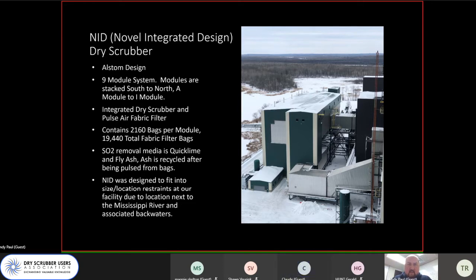It's a 9-module system with one redundant module, so we can maintain full load with 8 modules in service and take one out for maintenance. We stack that up A to I down the line, south to north. Each module has 2,160 bags, for a total of 19,440.